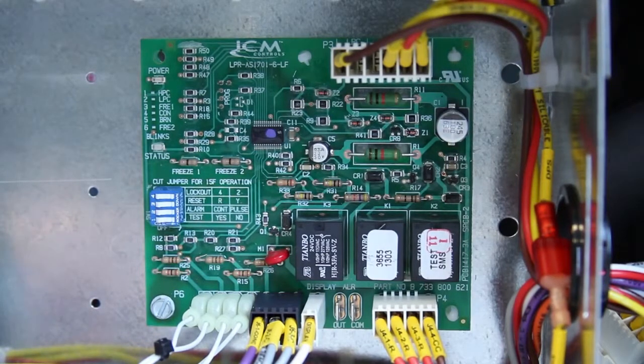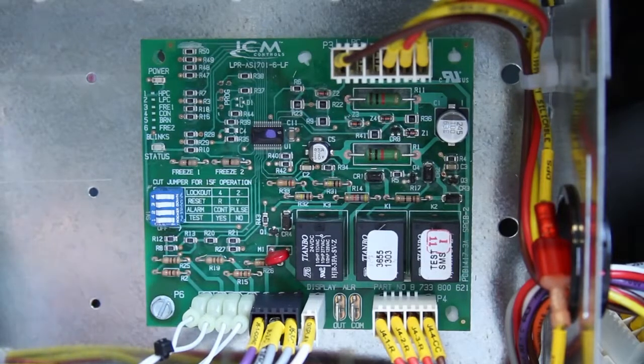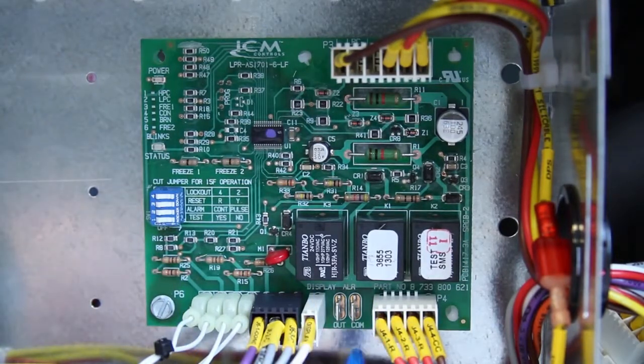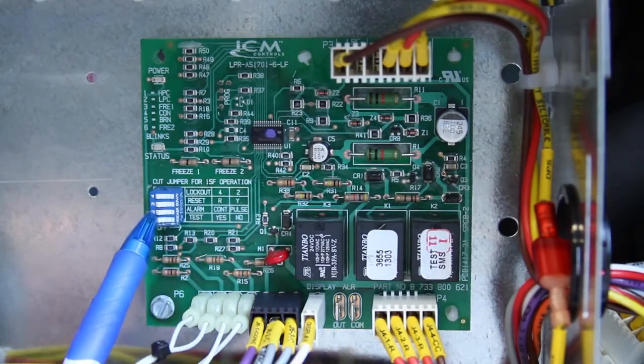Also, anytime there is a fault or a safety that has tripped and it is in a soft lockout or a hard lockout, we have an alarm output. It's located at the bottom of the board on these 2 open terminals. It's just a set of dry contacts. Anytime it's in a fault, it will pulse and open and close those contacts. You can also set dip switch number 2 from pulse to continuous, and those contacts will remain closed continuously during a lockout or a fault.